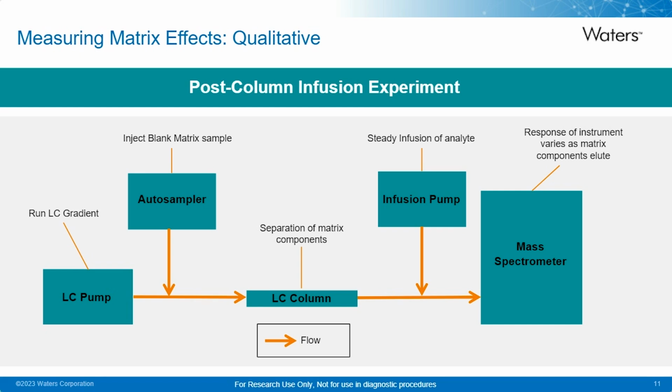Rather than inject it in the normal way, however, after the LC column, we will infuse a standard solution of the analytes and internal standards through a T-piece into the LC flow, which then goes into the mass spectrometer. What this does is that rather than having a background being quite low, it will actually raise this background up because you have that constant stream of your analytes being detected.